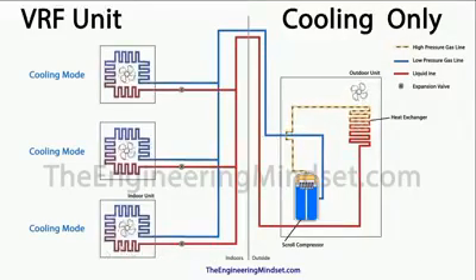Now as the refrigerant passes through this heat exchanger, or any of these heat exchangers, and it begins to leave the unit, the refrigerant will then leave and join this pipe as a low pressure, low temperature saturated vapor. And the constant force of refrigerant entering into this loop is going to force that refrigerant to continue and circulate back around into the scroll compressor, where it will be regenerated and pushed out again to complete the loop. And there you have it, the most simplest version of the cooling only VRF unit.